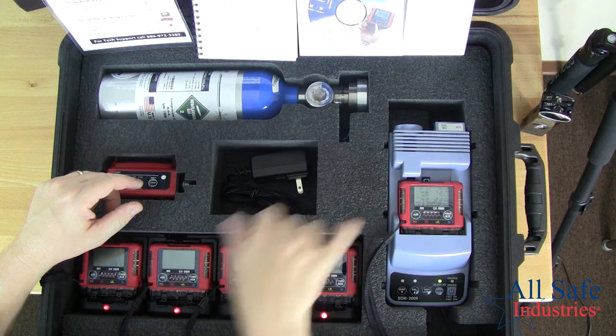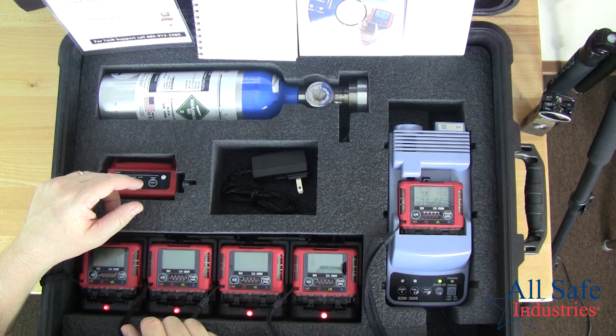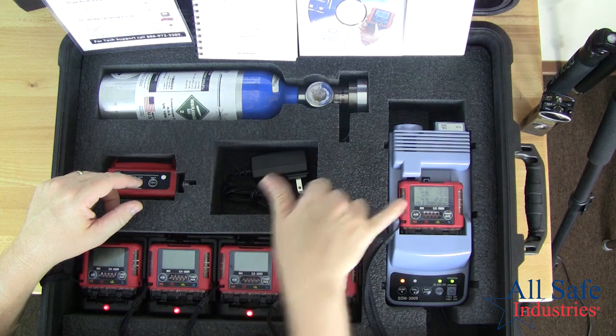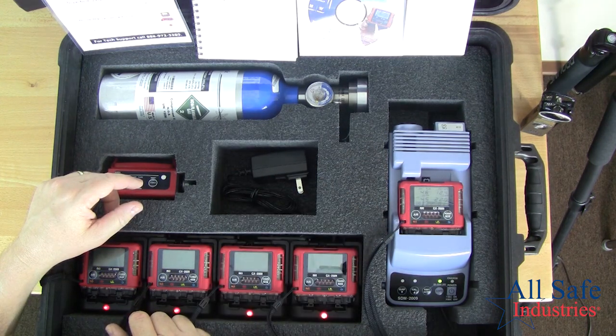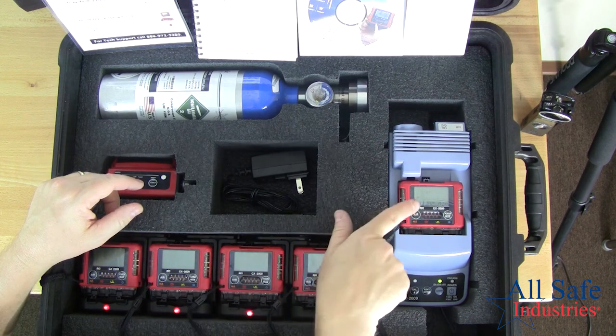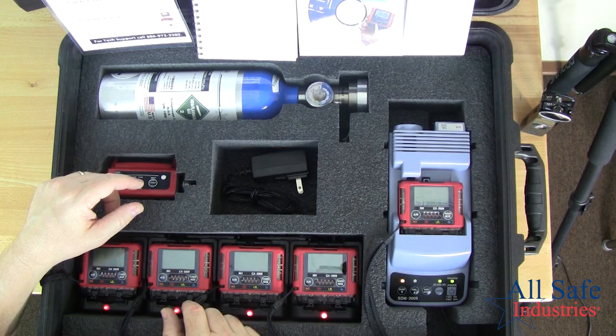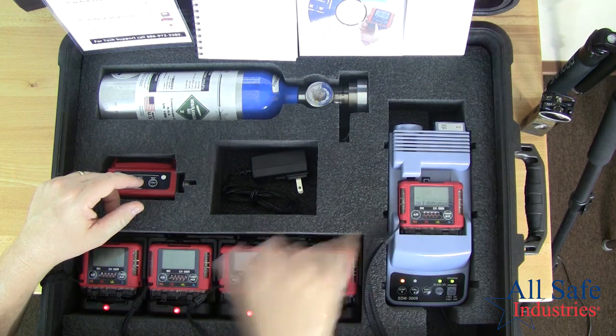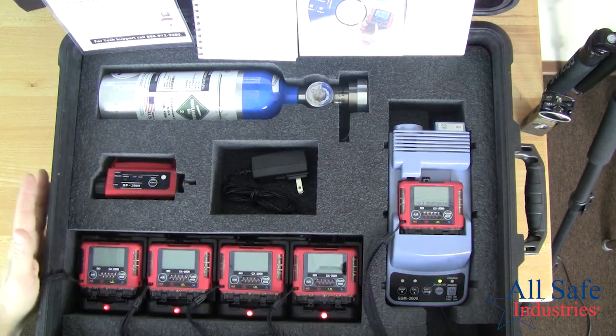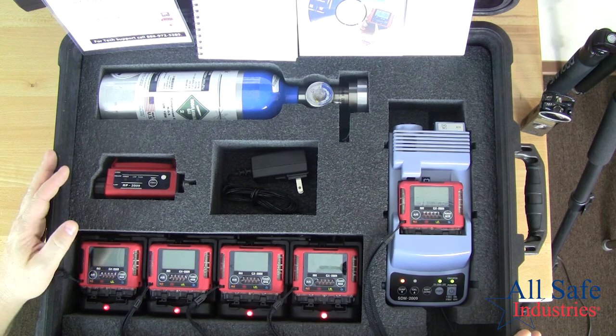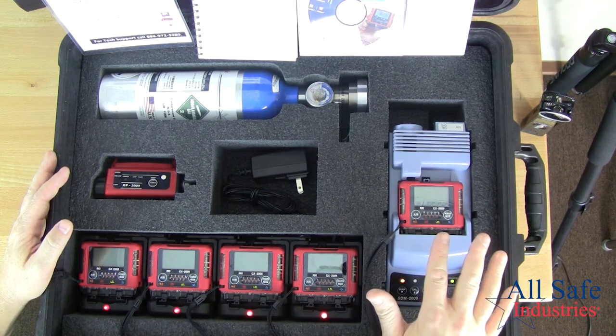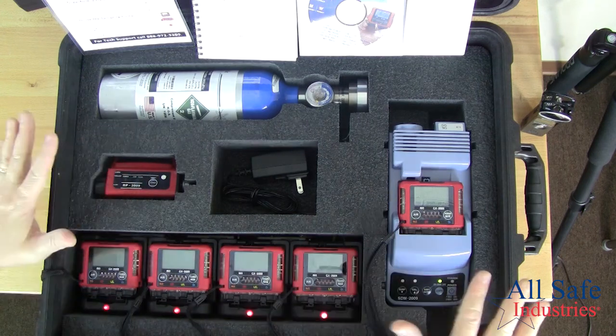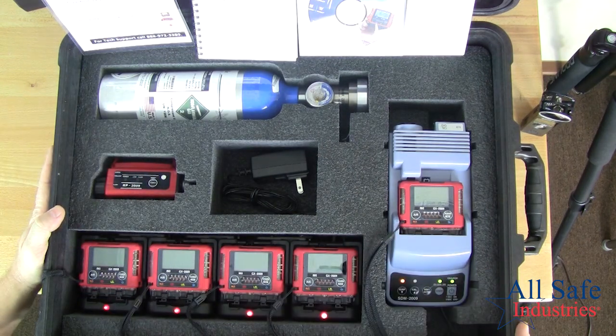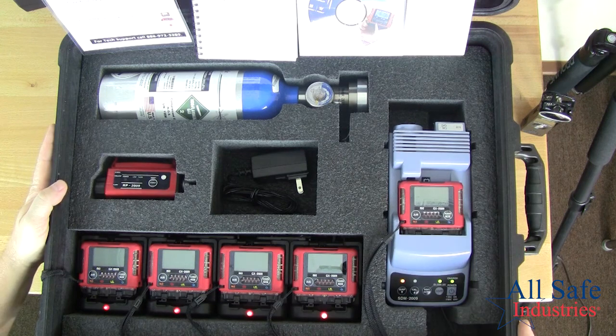I just let the cal station do all the work for me. At the end of this, when it reaches full scale, it will recognize that the bump check passed, and it will say P or pass on all the channels, and then we'll get a green light down here on the bump. And then at the end of the sequence, it will run fresh air one more time, and then at the end of the sequence this will just power down. So this is a nice upgrade to the kits that you already have. If you want to add a cal station, if you want to add a pump module, this just takes your GX-2009 kit to the next level by adding these other accessories.